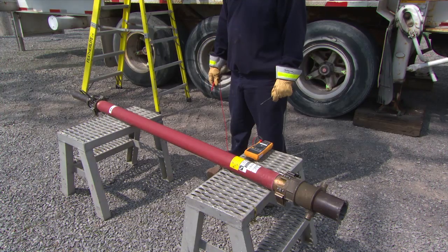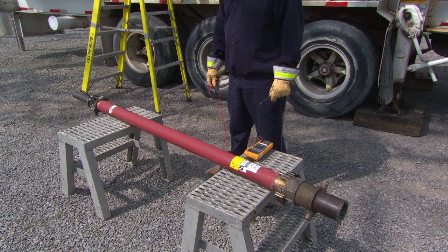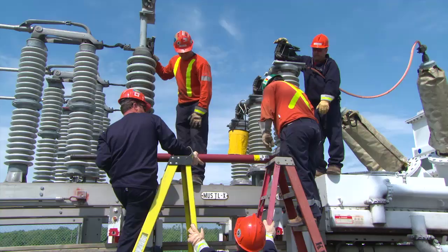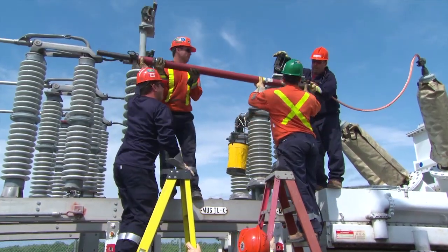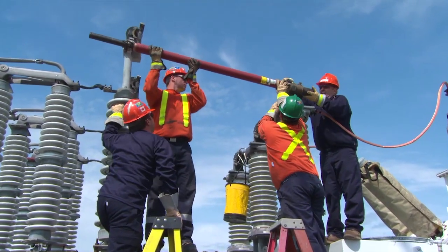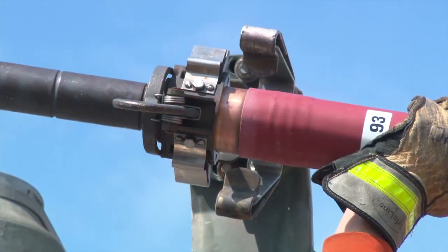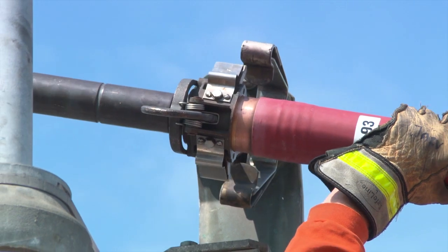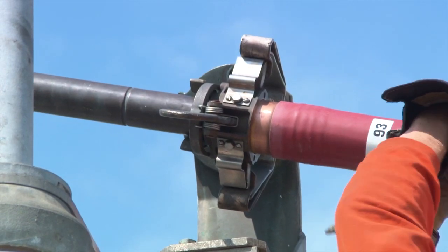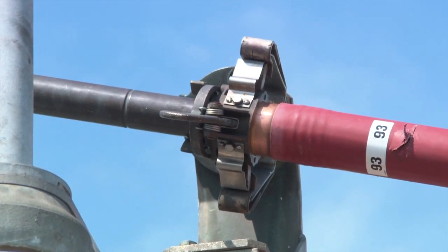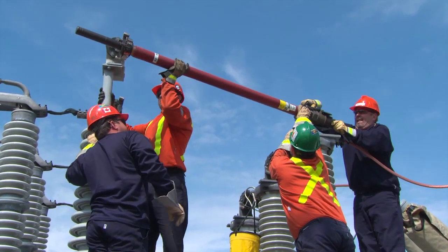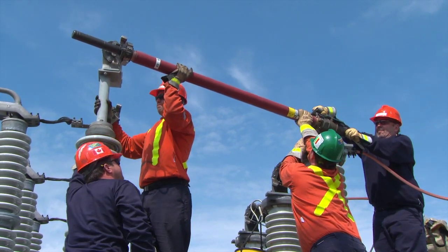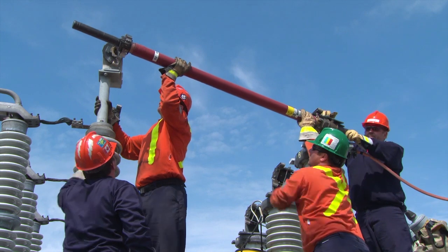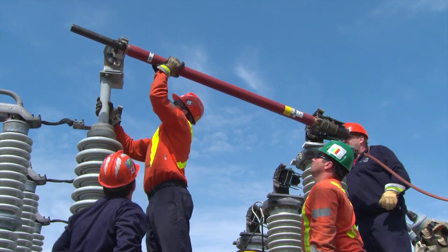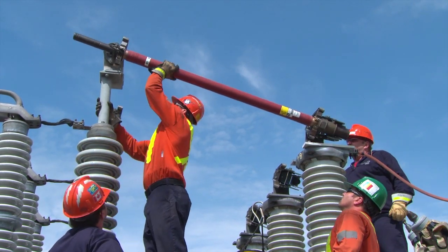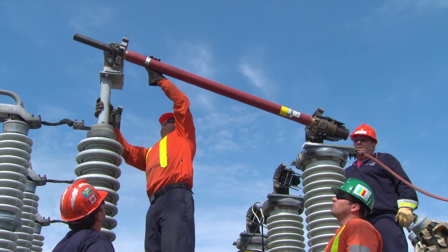And test for continuity using a digital multimeter. Once you have inspected and tested the fuse, raise it into position and place it in the jaws. This may require some finessing. Ensure all fuses are latched securely in the closed position.